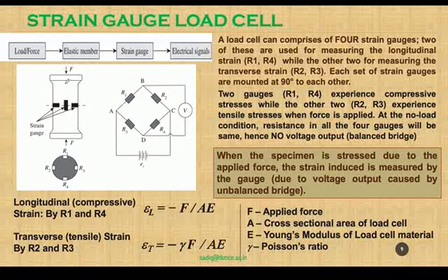Now, in the strain gauge load cell, as we see here, there is a force element, force applied here. There is an elastic member. This is the elastic member. When there is force applied on that, there will be strain happening for the elastic member. Thus, there are strain gauges attached on the elastic member. So when there is strain on the elastic member, that will be transferred to this strain gauge. These strain gauges are attached as part of a Wheatstone bridge.